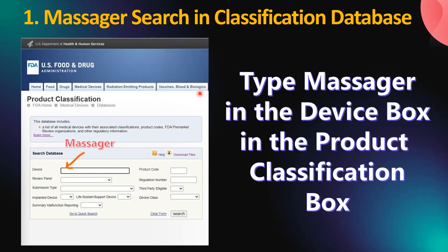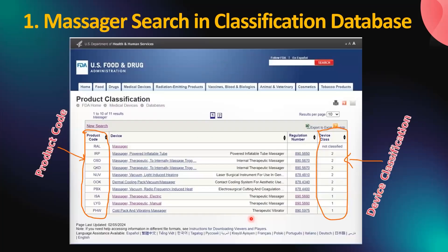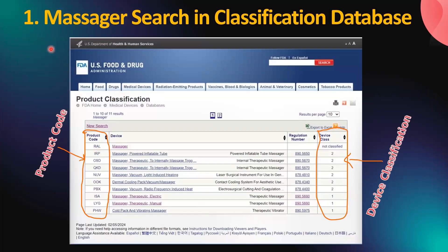First is the U.S. Food and Drug Administration product classification system. Using the example of a massager, type 'massager' in the device box in the product classification search. There are several other boxes you can fill based on available information, including the review panel, submission type, product code, and regulation number. When you hit search, it returns results showing information about different types of massagers based on their risk classification manifested as device class, taking into consideration general controls, special controls, and pre-market approval if required. There is also a product code linked with the massager types.